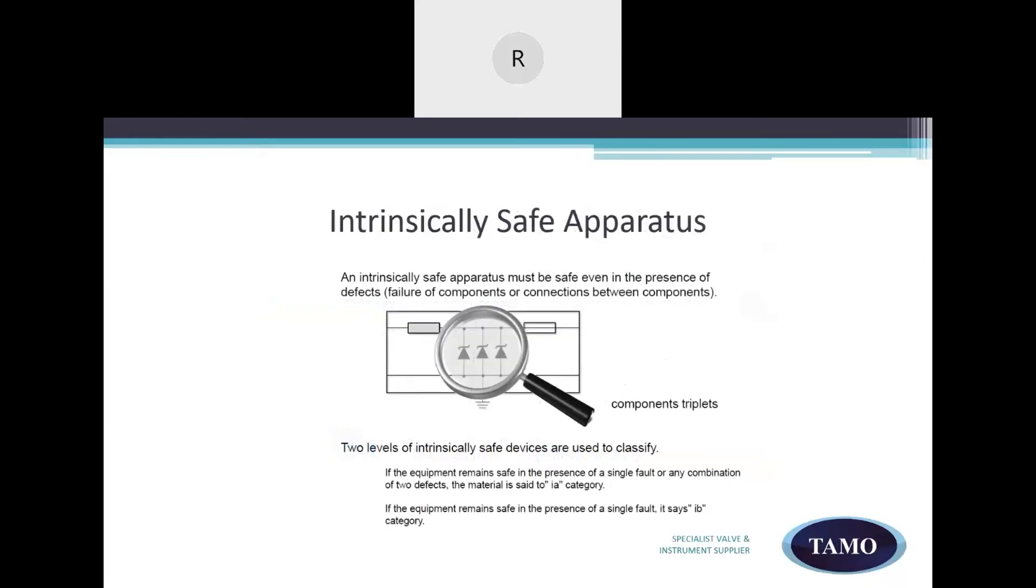The intrinsically safe apparatus. An apparatus must be safe even in the presence of defects or failure of components or connections between components. Two levels of intrinsic safety devices are used to classify. If the equipment remains safe in the presence of a single fault or any combination of two defects, the material is said to be ATEX IA category. If the equipment remains safe in the presence of a single fault, it is classed as ATEX IB category.